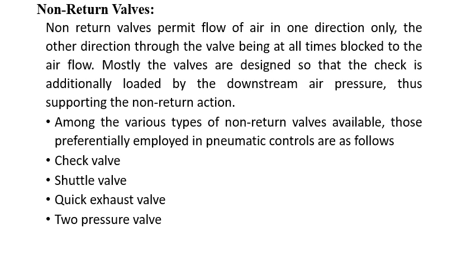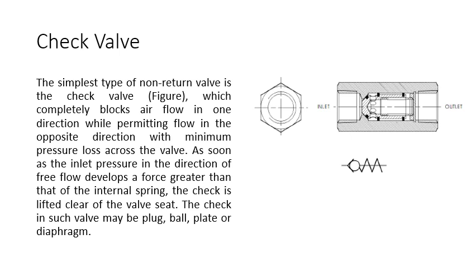The non-return valve allows flow of air in one direction only; the other direction is always blocked. These valves are designed so that the check is additionally loaded by the downstream air pressure, thus supporting the non-return action. Among the various types of non-return valves available, those preferentially employed in pneumatic controls are: check valve, shuttle valve, quick exhaust valve, and two-pressure valve. The simplest type of non-return valve is the check valve, which is shown in the figure — it has a spring-loaded moving component.